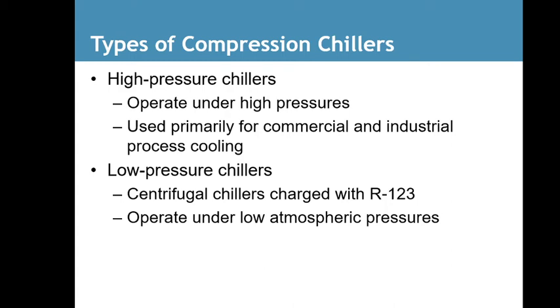Types of compression chillers. High pressure chillers operate under high pressure, used primarily for commercial and industrial process cooling. Low pressure chillers, centrifugal chillers charged with R123, operate under low atmospheric pressures.